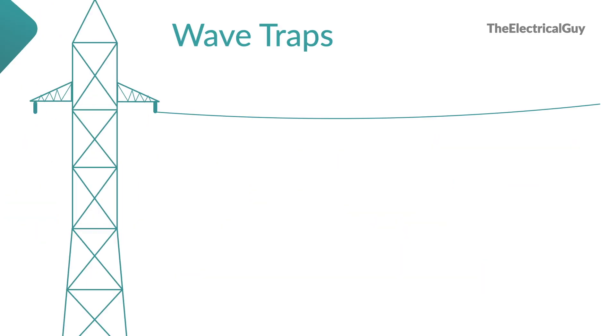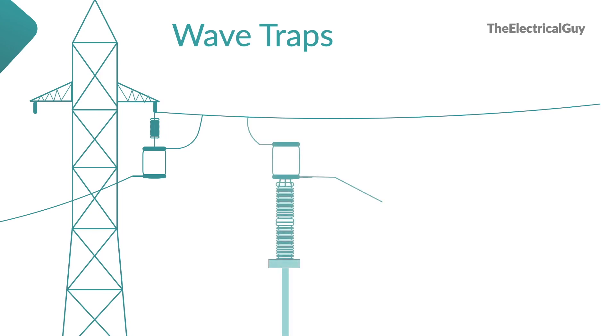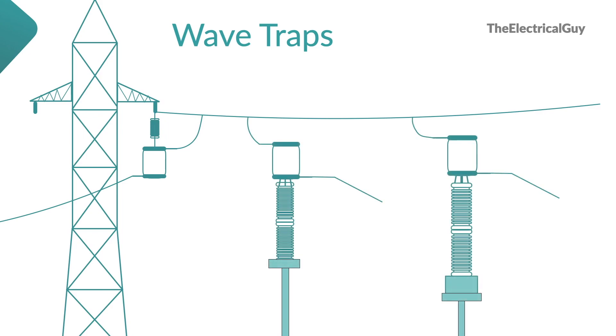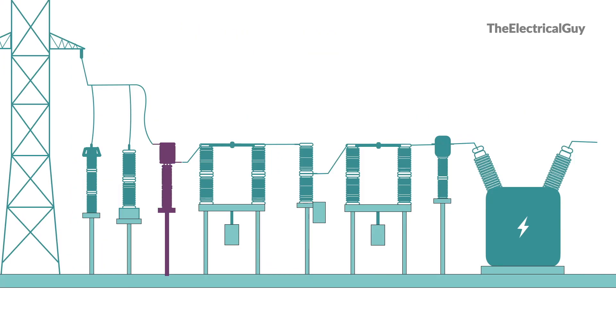You may see different ways of mounting wave traps. They can be mounted on the gantry, on a separate support structure, or on the capacitive voltage transformer. With the help of a coupling capacitor or CVT, these high frequency signals can be transmitted or received by a communication device.